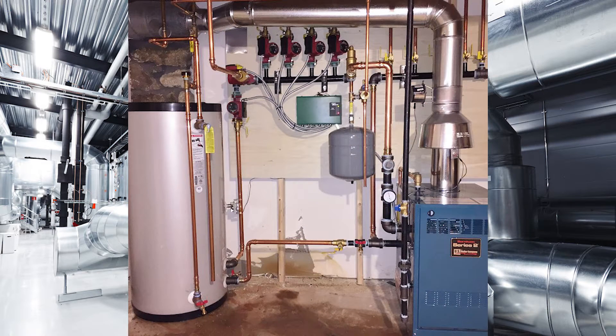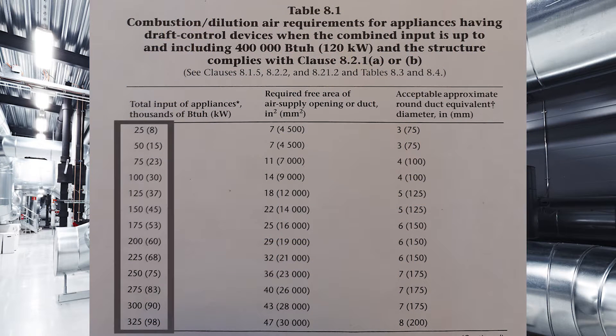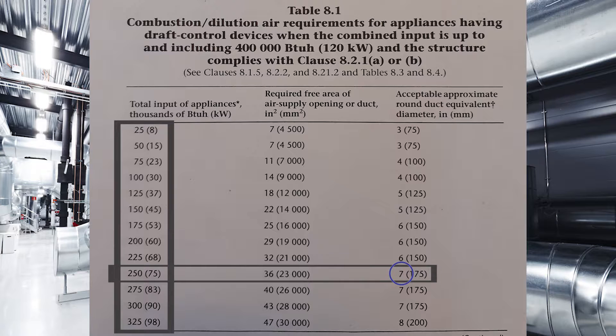Let's size some up. My first example is a drafthood equipped boiler that is 240,000 BTUs. Because my boiler is equipped with a drafthood, I'm going to use table 8-1. I go down the far left column to 240,000 BTUs — it isn't there, so I go to the next size larger, which is 250, and go right across to the far right column. I need a 7-inch round duct air supply.